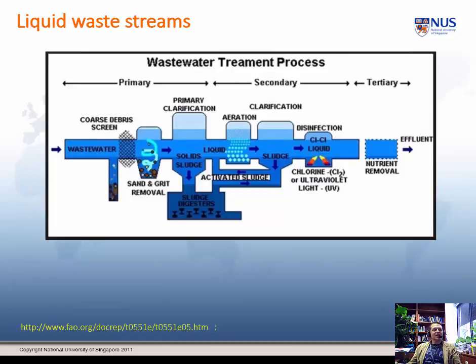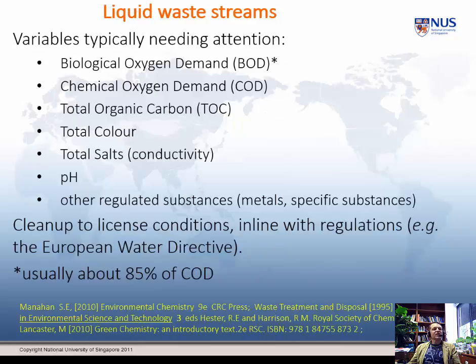And this is what it might look like picturesquely. You've got your preliminary treatment, and in this diagram preliminary has been bulked with your primary. So you've got your filters, your sand and grit removal, and then your first primary process — the anaerobic digestion to sewage and sludge. It goes on with aerobic digestion in the secondary stage, producing more sludge. When you've got sludge from an aerobic process it's usually called activated sludge. And then finally there's disinfection — they've got chlorination and ultraviolet light as their polishing for discharge. Their tertiary or advanced stage has nutrient removal.